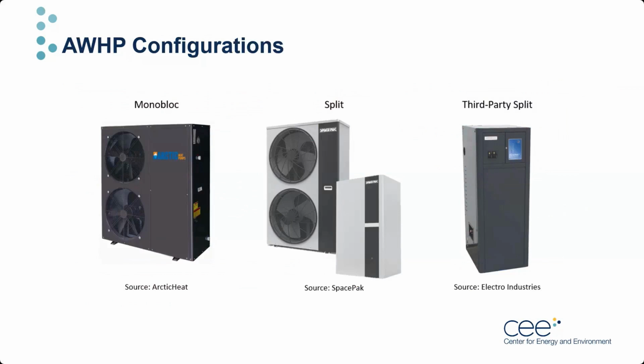Here are some examples of air-to-water heat pump products from Arctic, SpacePak, and Electro Industries. There are two main air-to-water heat pump configurations, which we will call either monoblock or split systems. In a monoblock system, the refrigerant-to-water heat exchanger is inside the outdoor unit, or ODU, and what you get is all the important bits packaged in a single, kind of large box outside the home, and hydronic fluid is what crosses the envelope. In a split configuration, the refrigerant-to-hydronic heat exchanger is inside the home, and refrigerant crosses the building envelope. The indoor heat exchanger is packaged with other system components in what we call the indoor unit, or IDU, which is the smaller box in that middle picture.